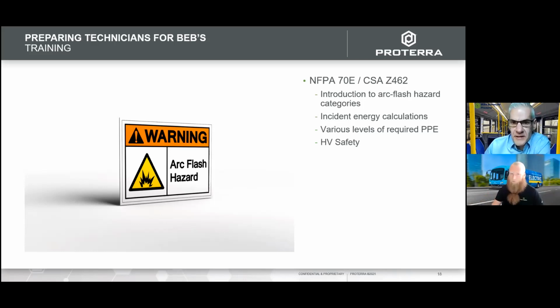James, another question, I'll try and get this one right, but how long does it take to de-energize a bus once locked out, tagged out? So it really varies. On our buses specifically, you can technically de-energize a bus within 5 to 10 minutes. We build in that 5 to 10 minute window solely for the fact that if there is a failed resistor circuit to bleed down any of the capacitors in the inverters, it's had time to discharge the capacitors. As long as the resistors and everything in there are working properly, you could have a bus locked out and de-energized in that 5 to 10 minute range. It's very quick for our inspection.